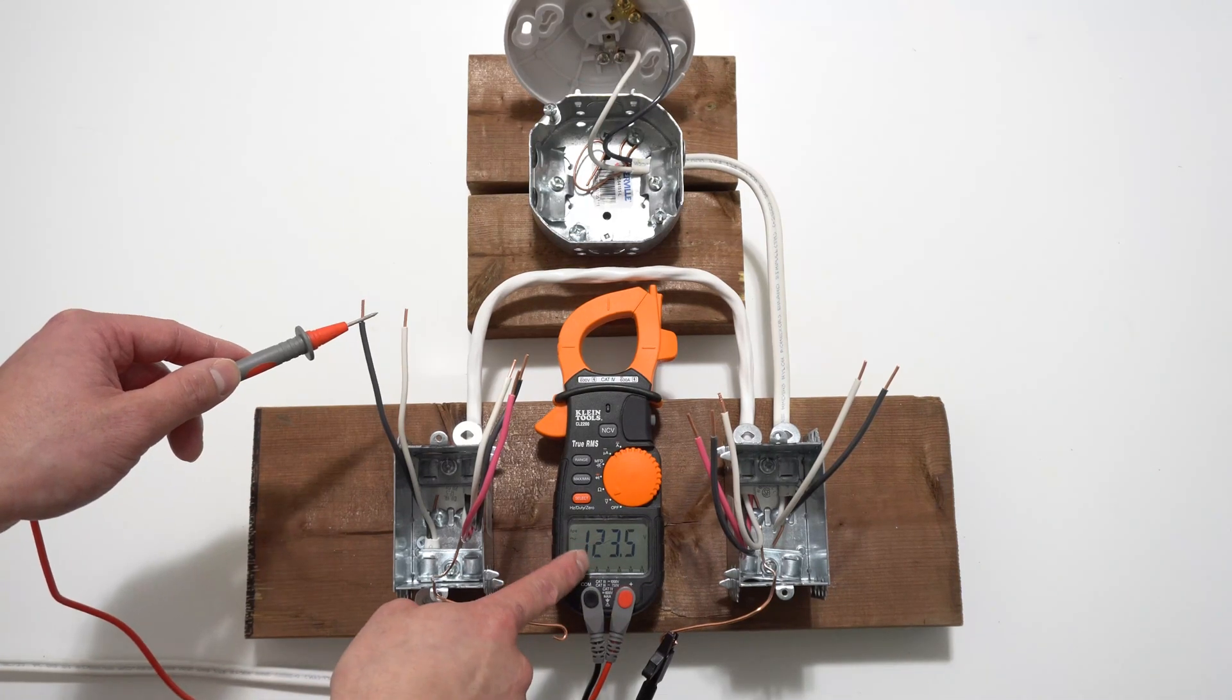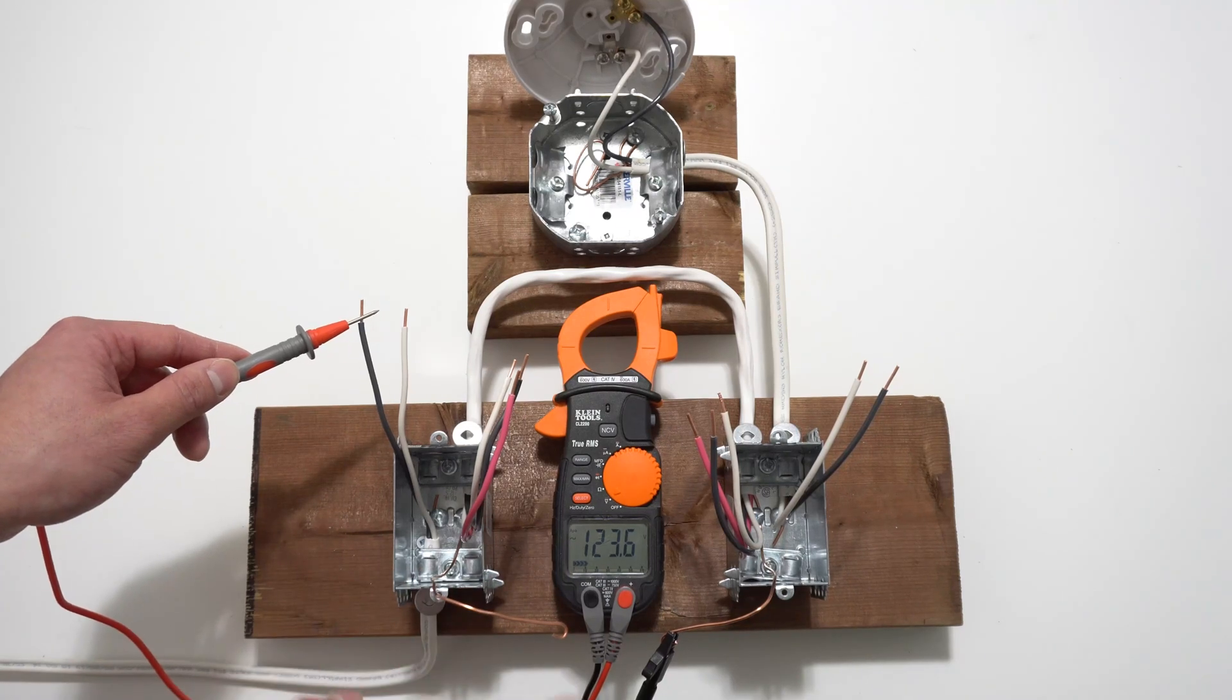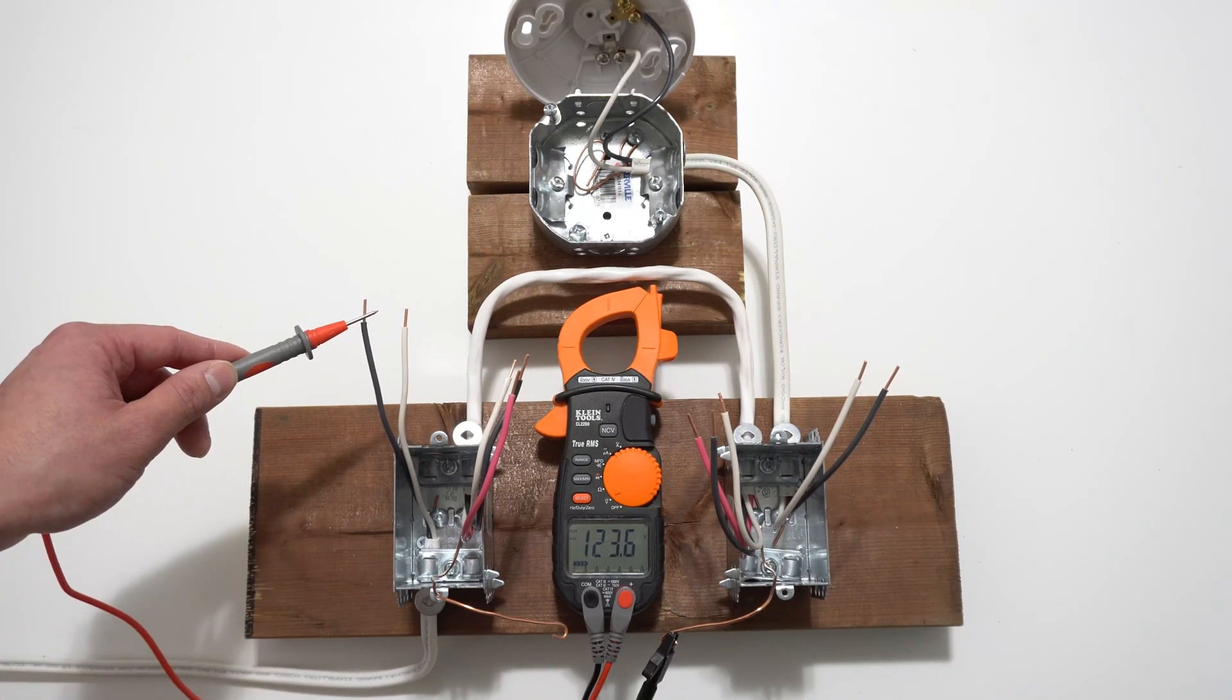And here we have, touching the last wire, we have a potential difference of 123. So the circuit is still live. So you want to double check the circuit breaker and turn off the right one.